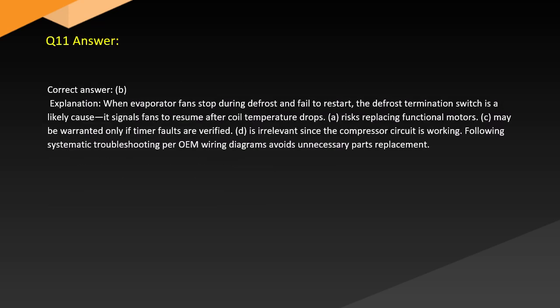Answer. Correct answer: B. Explanation. When evaporator fans stop during defrost and fail to restart, the defrost termination switch is a likely cause, as it signals fans to resume after coil temperature drops. A. Risks replacing functional motors. C. May be warranted only if timer faults are verified. D. Is irrelevant since the compressor circuit is working. Following systematic troubleshooting per OEM wiring diagrams avoids unnecessary parts replacement.